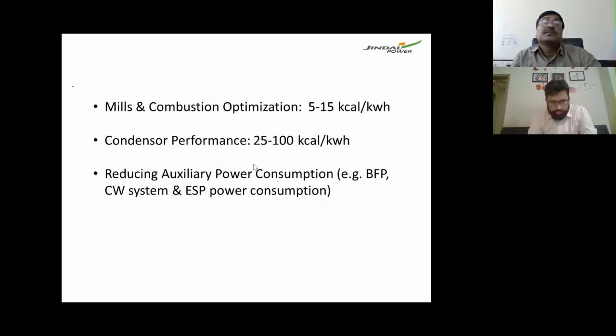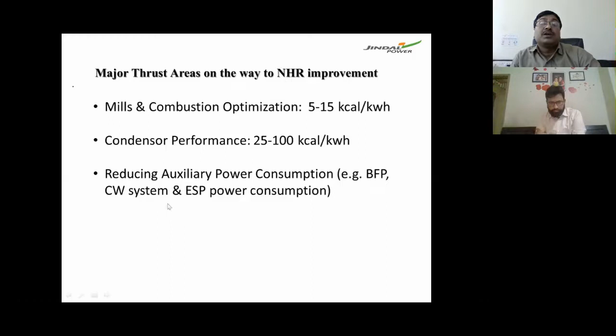The major thrust on the way to net heat rate improvement: basically, we should consider these three things more and more. Although all other things are very important, these are the most important because they account for around 5 to 15 kilocalories of savings in the whole combustion process. So this should be very closely monitored and optimized. The condenser only accounts for around 25 to 100 kilocalories. And there is potential in auxiliary power saving also, generally in the BFP system and ESP power system.